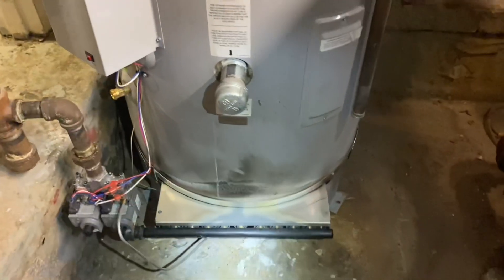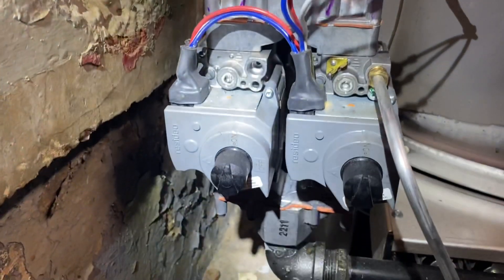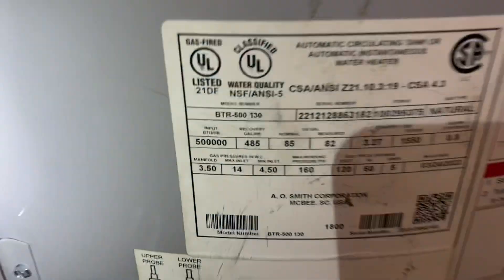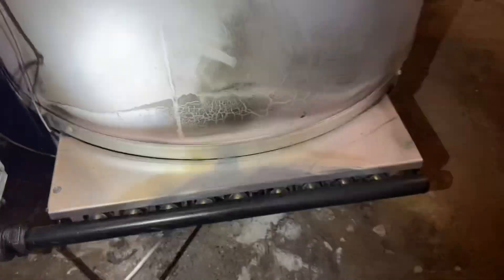So what happens when you turn this thing on? Oh, this is the one with the rollout — the flame comes out. This came with the original water heater? Okay, that's a replacement and it still does the same thing. You've got the Honeywell dual gas valves for 500,000 BTUs. Yeah, so it's got a good flame rollout there too.